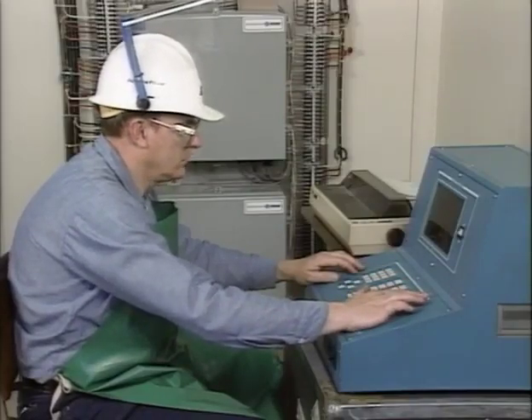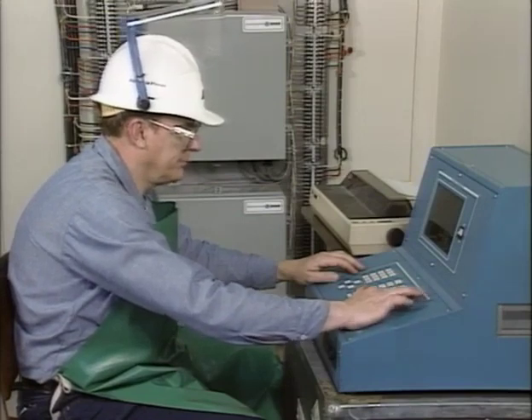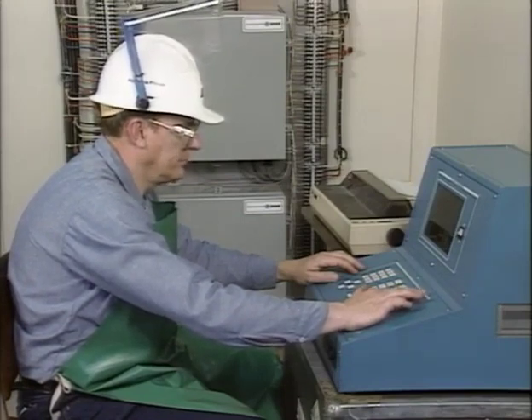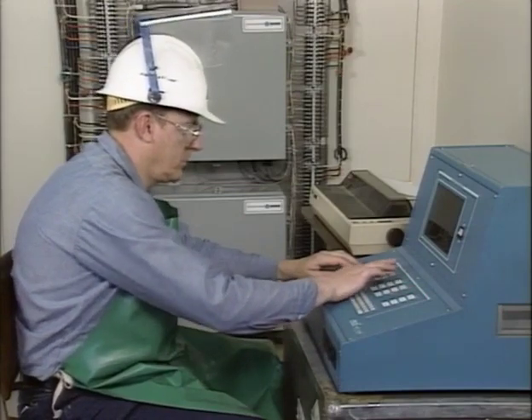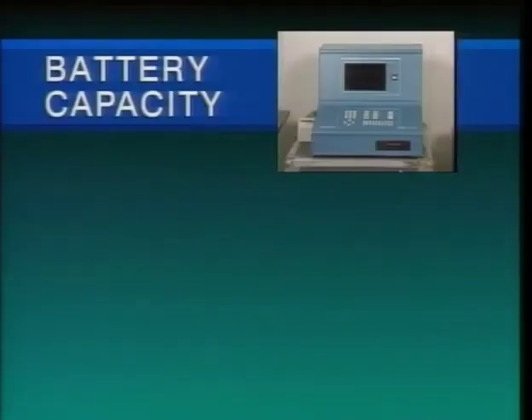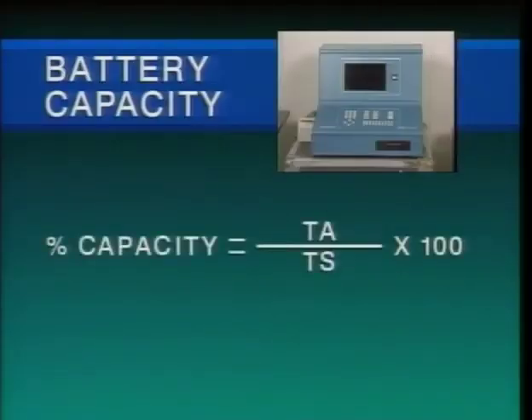The time that the test was interrupted is noted so that it can be subtracted from the total test time when battery capacity is calculated. The test is done when the battery reaches its minimum acceptable value, in this case 42 volts, or when the test time expires. Battery capacity is then calculated using this formula. Percent capacity equals TA over TS times 100. TA is the actual time it took for the battery to discharge to the minimum voltage.